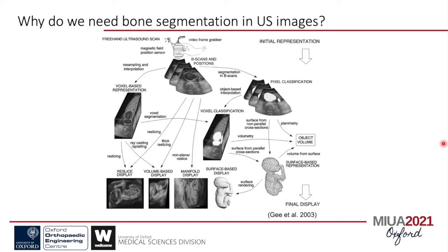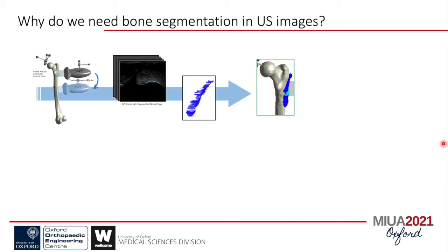3D freehand ultrasound has been developed for years. This diagram demonstrates a system that reconstructs 3D volumes with a freehand scan. We now take a step forward: take a freehand ultrasound sweep, record the probe position with an external localizer. By performing bone position segmentation in the image and registering all images in 3D space, we can build a 3D model.